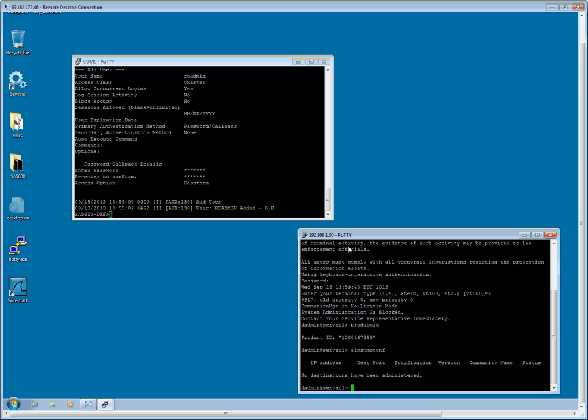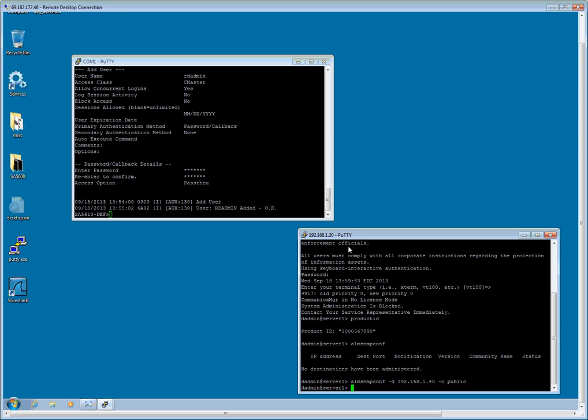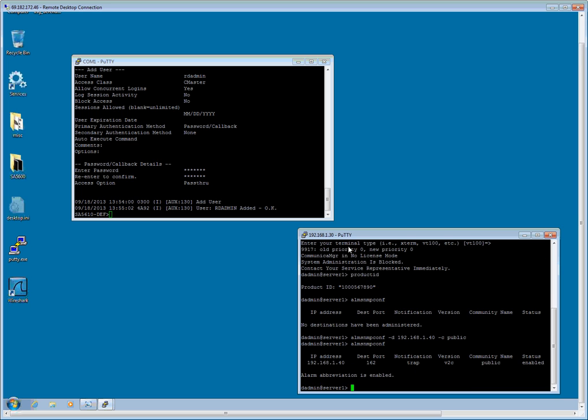So I am going to enter ALM SNMP CONF. I am going to use the D switch for the IP address. So dash D and 192.168.1.40. And I am going to use the C switch for the community string, which is going to be public. And I will hit enter. Now I will go ahead and verify that with just entering the command again, ALM SNMP CONF. And I see that we are now configured.